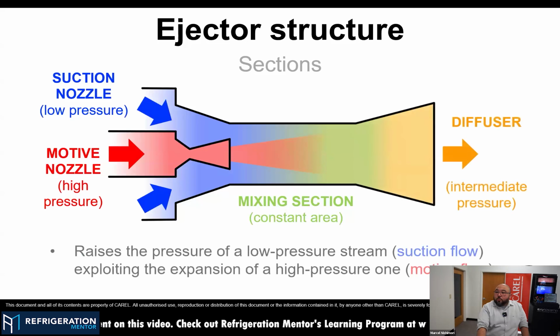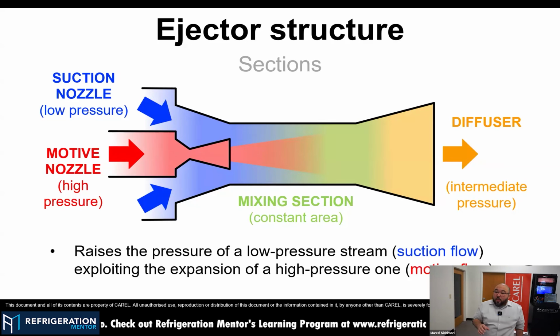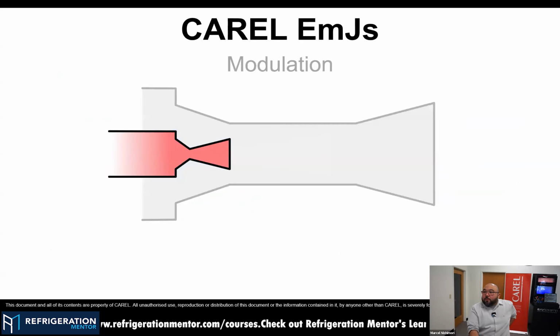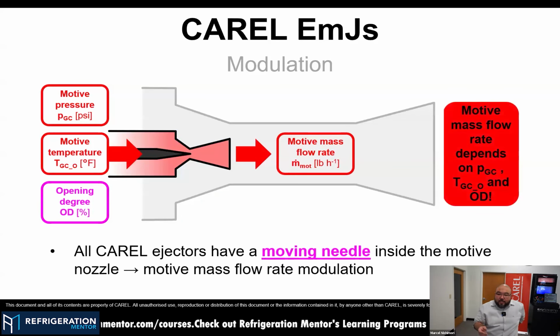Yeah. So here I'm just showing you again what we are doing in terms of fixed conditions, and consider that this example here, this first picture, is what we call a fixed ejector behavior. So there is no device metering the amount of flow from any of the parts. So what CAREL does with a modulating ejector is add a needle inside the flow that comes from the gas cooler side, and this needle is used with a stepper motor to control the flow inside the ejector. This needle gives the ejector the capability to act as an HPV valve in all conditions. So this needle will be controlling the gas cooler flow over to the liquid receiver, and will be adjusting the pressure according to what's needed.